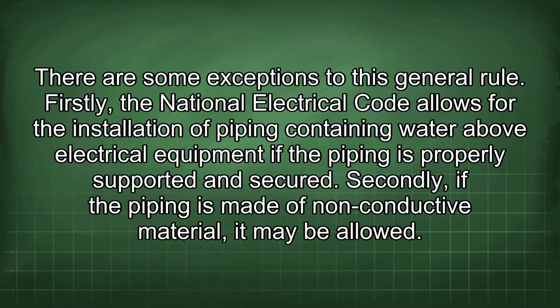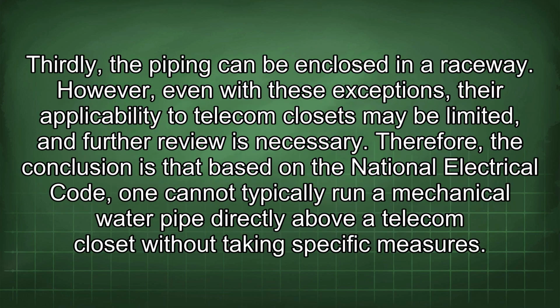Firstly, the National Electrical Code allows for the installation of piping containing water above electrical equipment if the piping is properly supported and secured. Secondly, if the piping is made of non-conductive material, it may be allowed. Thirdly, the piping can be enclosed in a raceway. However, even with these exceptions, their applicability to telecom closets may be limited, and further review is necessary.